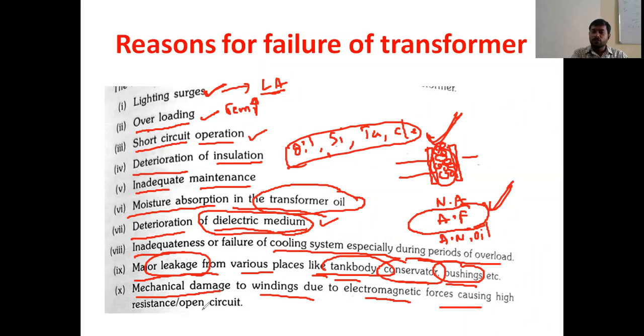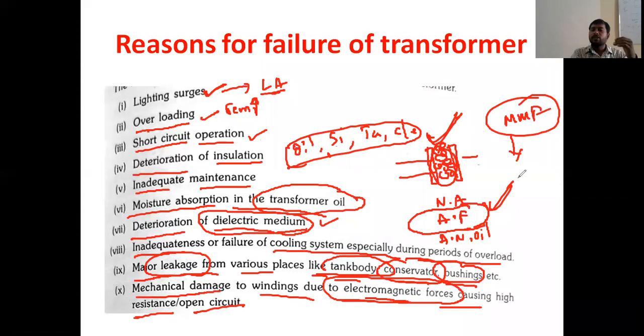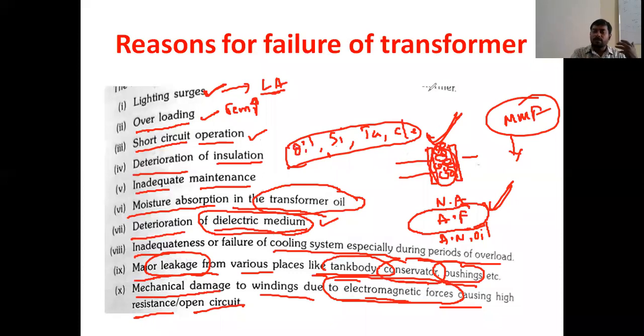The next cause is mechanical damage to the winding due to electromagnetic forces, which causes high resistance and open circuits. These electromagnetic forces — high MMF (magnetomotive forces) — and due to the magnetostriction phenomenon, the transformer gets vibration. Because of that problem, the transformer will get damaged.